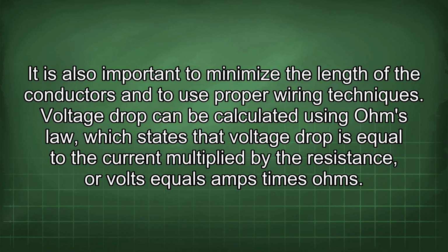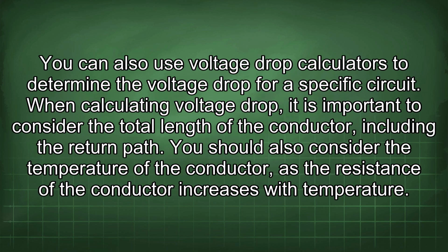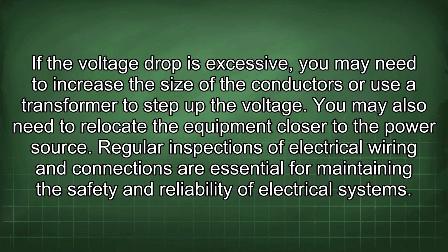Voltage drop can be calculated using Ohm's law, which states that voltage drop is equal to the current multiplied by the resistance, or volts equals amps times ohms. You can also use voltage drop calculators to determine the voltage drop for a specific circuit. When calculating voltage drop, it is important to consider the total length of the conductor, including the return path. You should also consider the temperature of the conductor, as the resistance of the conductor increases with temperature. If the voltage drop is excessive, you may need to increase the size of the conductors or use a transformer to step up the voltage. You may also need to relocate the equipment closer to the power source.